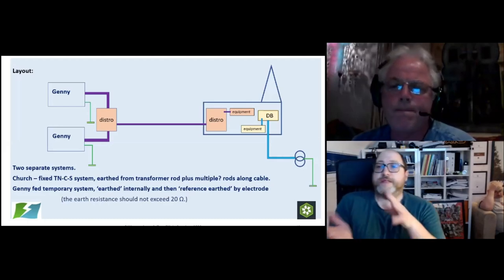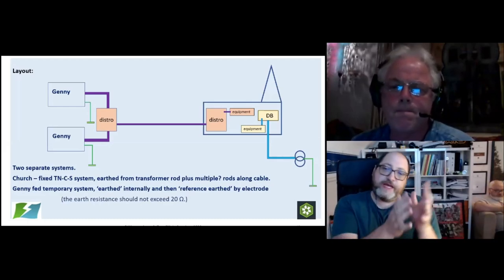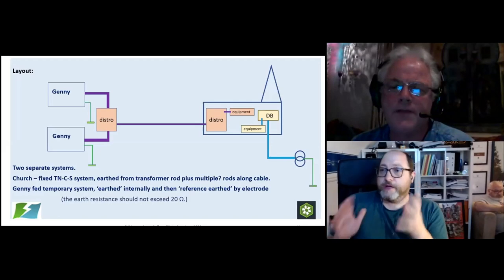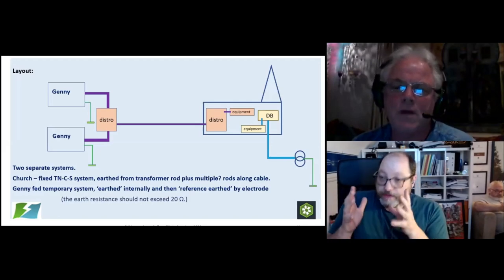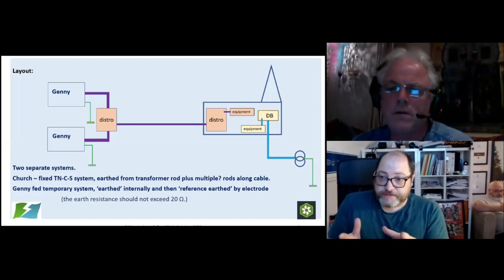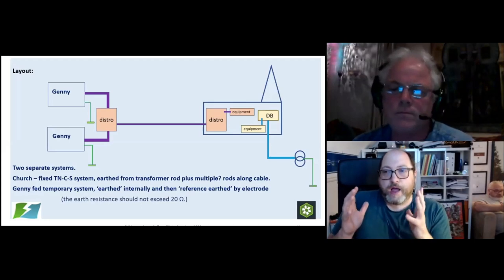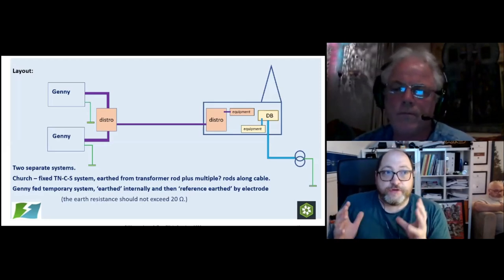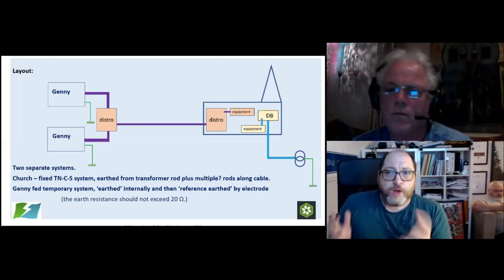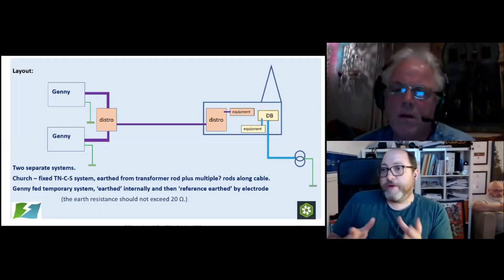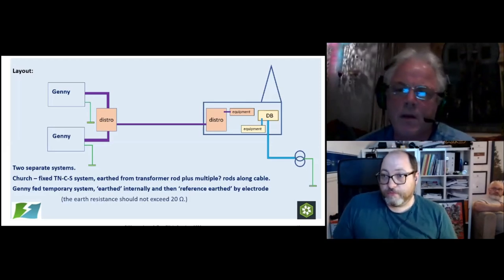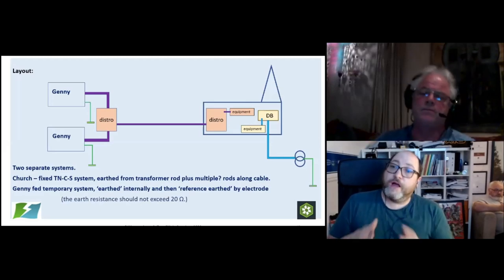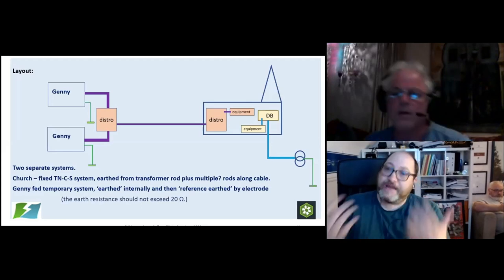Okay, so let's go for this. Let's say I've got a generator to an ISU, and I'm going to run a large cable that does not have instantaneous disconnection. Nope. If there's a risk of shock, I wouldn't install it. So let's say, for example, I'm going across a road. It's got to be protected. There's a risk of damage, risk of shock. I'm going to have to put in a ramp.